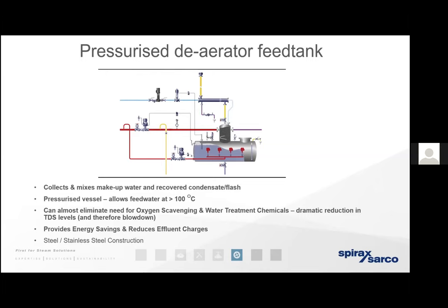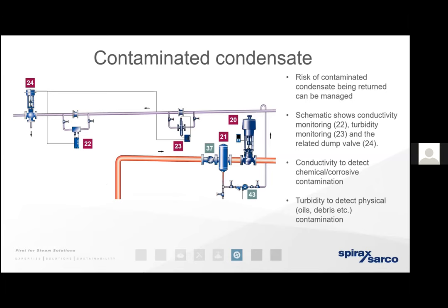We still have many clients dumping condensate to waste needlessly — typically through fear of contamination from oils, fats, or acids. We can now offer a contamination control system: a series of turbidity or conductivity probes that, when there's a contamination risk, send a signal to a three-port diverter valve to dump condensate to waste. When it's in good condition it can be recovered, and even when it must be dumped we can divert it across a heat exchanger to recover some of that heat energy.